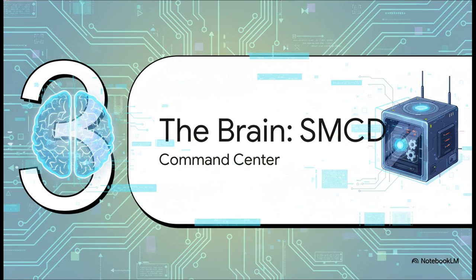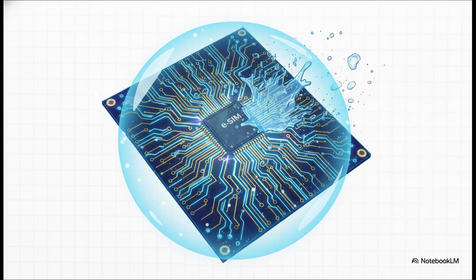All right, Section 3, the brain, also known as the SMCD. With our acronyms sorted out, let's examine the actual command center, the smart metering and controlling device. Think of this as the grid's neural network. Seriously, it's not just a basic meter, it is highly intelligent. It performs real-time energy audits right at the transformer level and handles remote communication back to a head-end system using both traditional SIMs and modern eSIM tech. It even has 2 programmable thresholds. One triggers an early warning alarm, and the other triggers a hard physical trip to protect the system. Oh, and since it lives outside in the elements, its printed circuit boards have a special conformal coating just to protect those delicate electronics from moisture and dust.